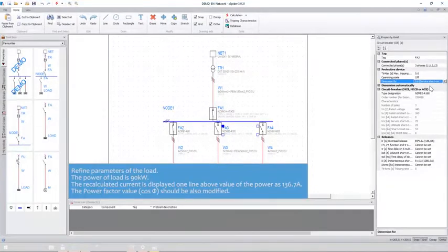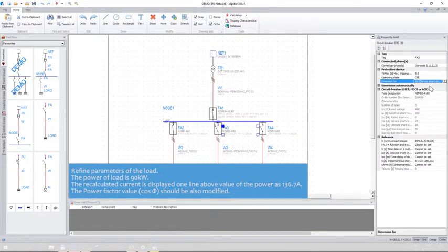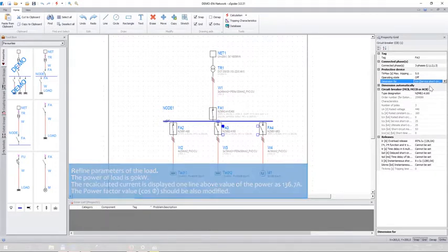Refine parameters of the load. The power of the load is 90 kilowatts. The recalculated current is displayed one line above the value of the power as 136.7 amps. The power factor value, cos, should also be modified.